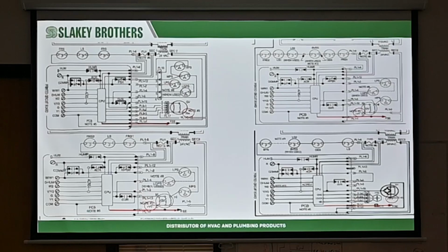But as you can see, this voltage comes from the circuit board. So even though it goes in series with a high pressure switch, that's for pressure switch proving. So no matter what, your flame should come on. Common to low first, and then common to high. So you got common to low, you got 24 volts and the gas valve won't open, you got a bad gas valve. On this one over here, it's just a hot and common.